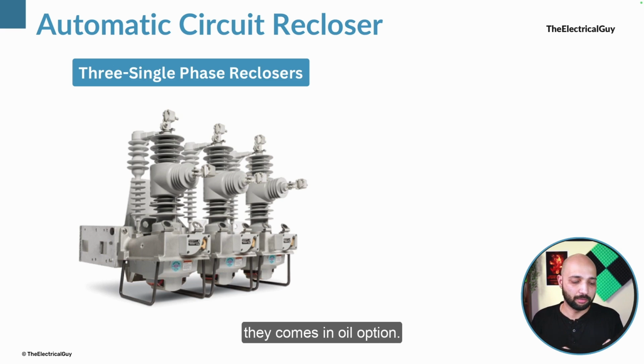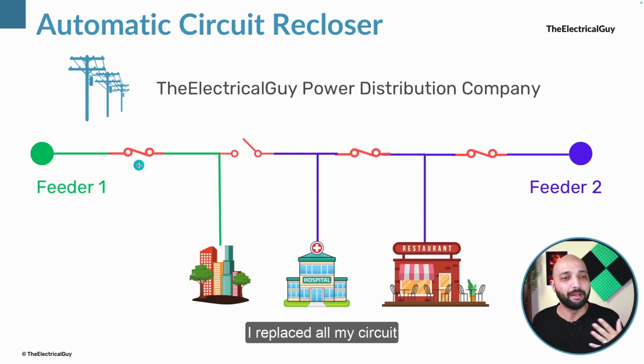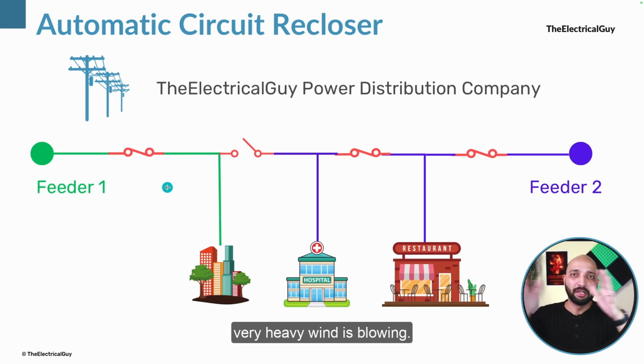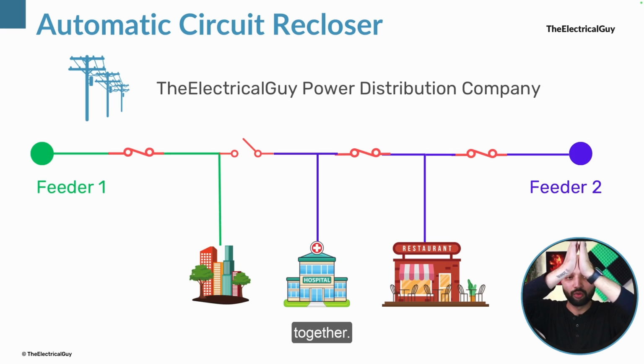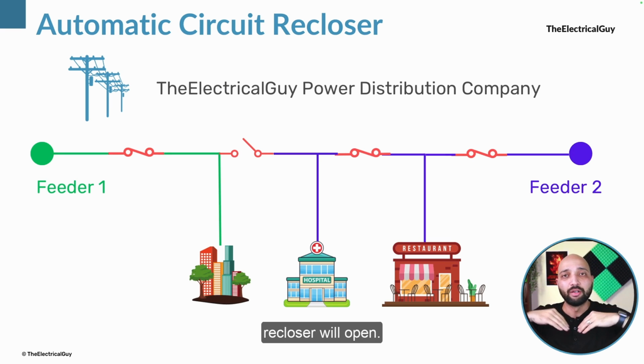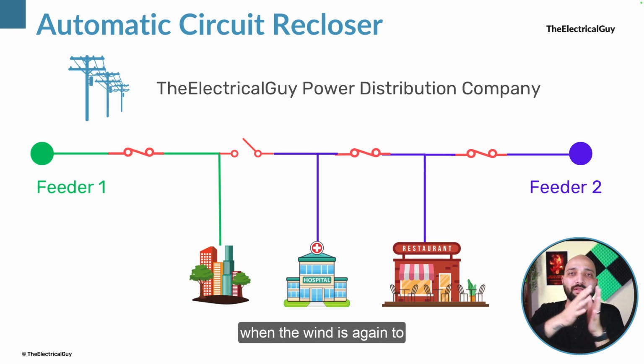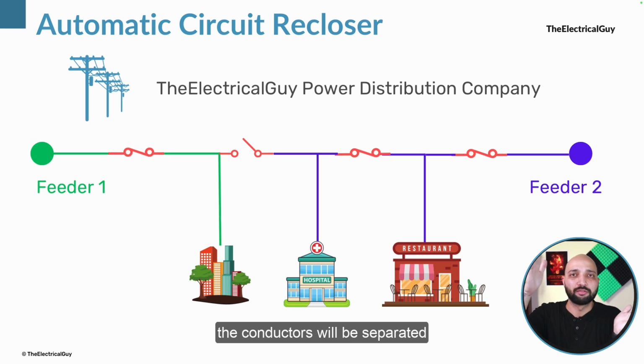And as I mentioned, they come in oil option, so oil for interruption and insulation medium, or vacuum for interruption and insulation medium. Now what is the advantage for my company if I use this recloser? For example, I replaced all my circuit breakers with reclosers. Now very heavy wind is blowing, two conductors are connected together, the system will sense it, the recloser will open. But after some time, when the wind is again in the normal condition, in a few seconds the conductors will be separated and the fault is automatically cleared.